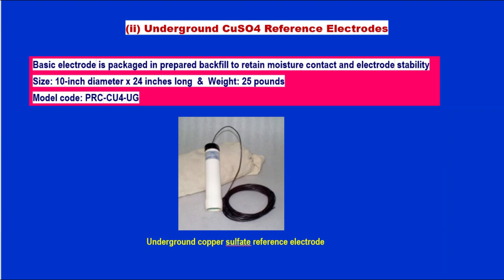The standard copper sulfate electrode is tested for ±10 mV. The underground copper sulfate reference electrode uses a prepared backfill to retain moisture, contact, and electrode stability. Size: 10-inch diameter, 24 inches long, weight 25 pounds. Model code: PRCCU4UG. The image provides a view of the underground copper sulfate reference electrode.